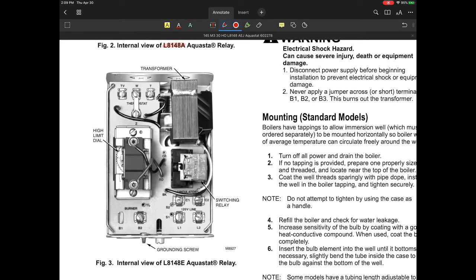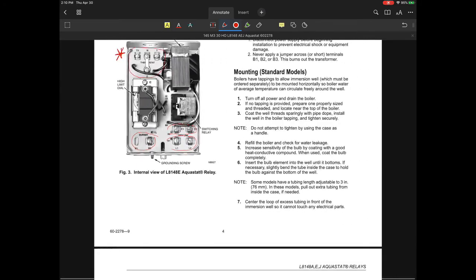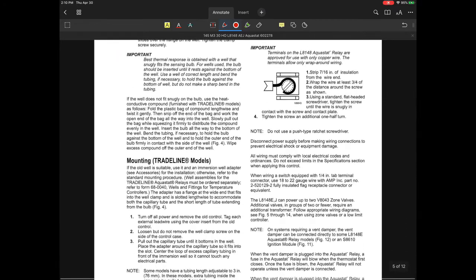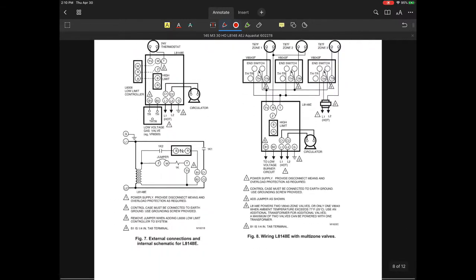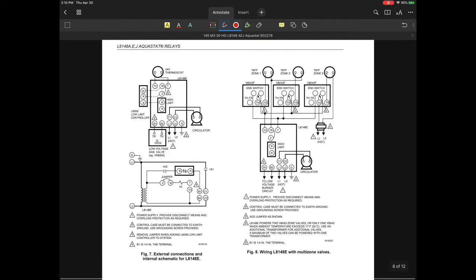What this one is going to show me is that between this one, with a little tiny transformer on the top, and this one, you now have a much larger transformer that allows some additional functions. You have thermostat demand terminals between T and T. You still have your burner circuit terminals. You have line voltage, L1 and L2, C1 and C2. A lot of it looks very similar. The big change is really up here, in this area. That's probably your biggest change.